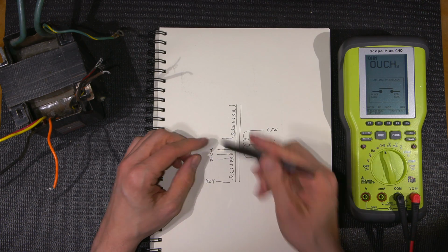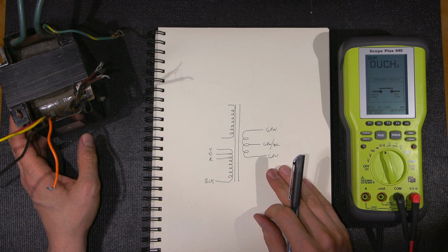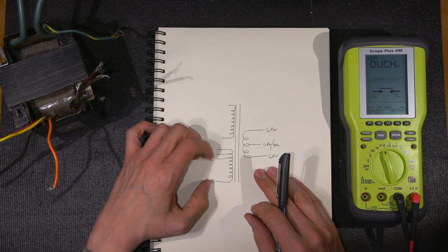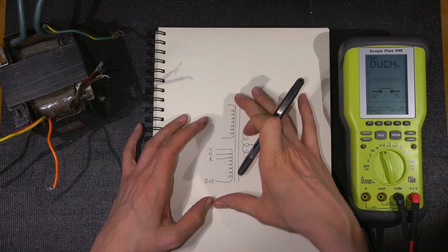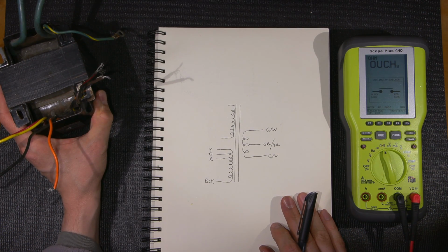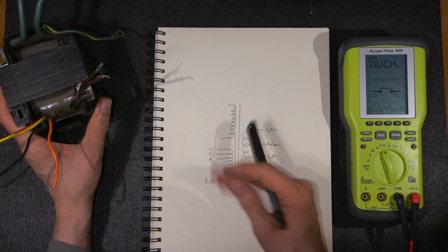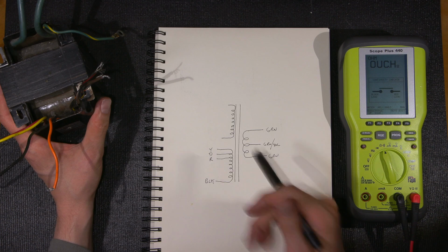Now, moving the taps around on this side, since they're so close together, really isn't going to cause much heating in the transformer. Say you were to run from black to red or from black to yellow, the difference in the heating of this core is going to be really quite minor because it's such a large transformer and the taps are so close together. They're really, really close together. So some more hints and tricks.